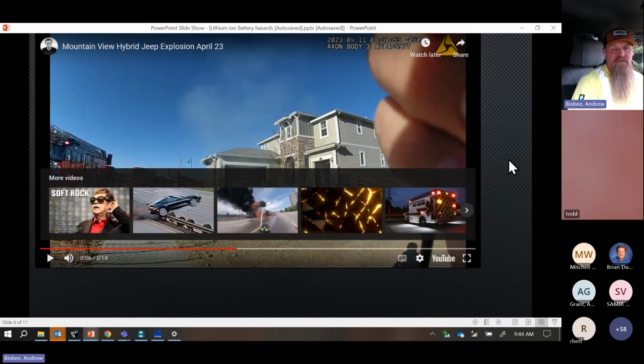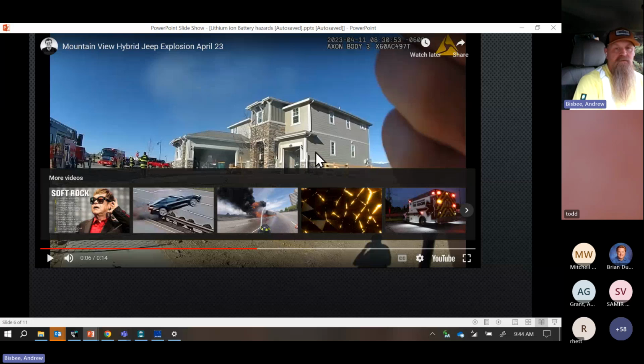So that garage had filled completely with hydrogen and carbon monoxide from that off-gassing. In my world, if the meter was on this side of the house and I went over there and pulled the meter for that electrical odor smell, there would be a 2-inch pipe going from that meter into the panel inside that garage. If I pulled that meter, the spark created from turning off their power would have blown my face completely off, because all that gas would have ignited and shot fire out that 2-inch hole. It so happens the meter was on this side of the house, but it could have been on that one. These are real concerns for me.